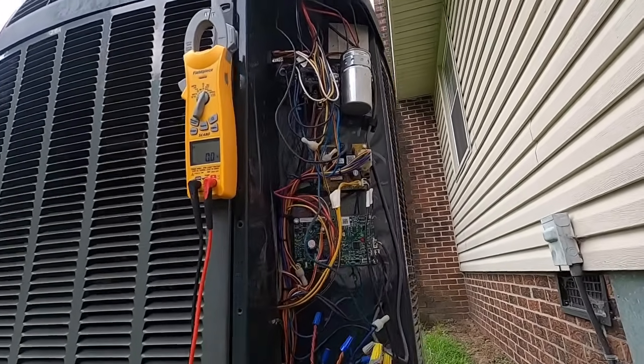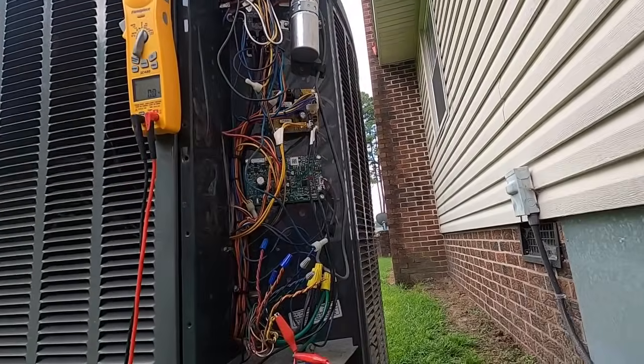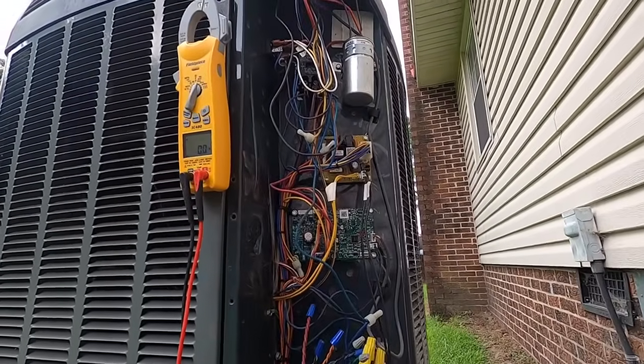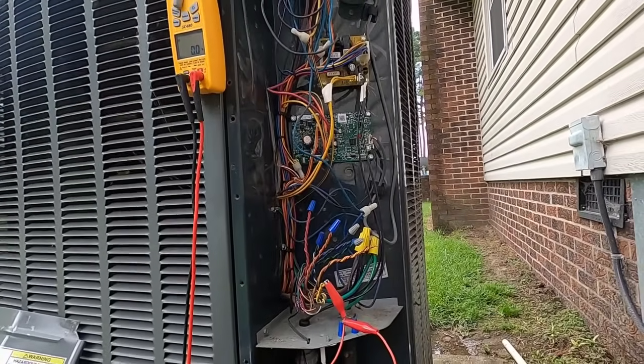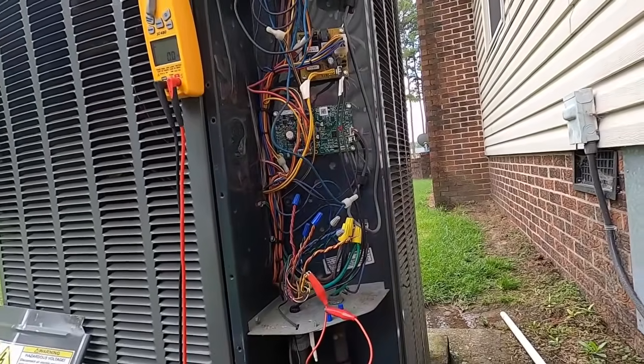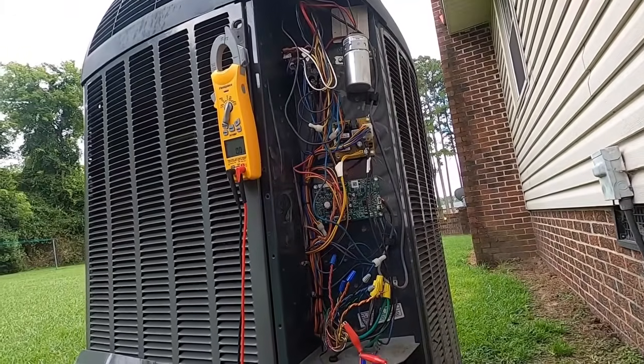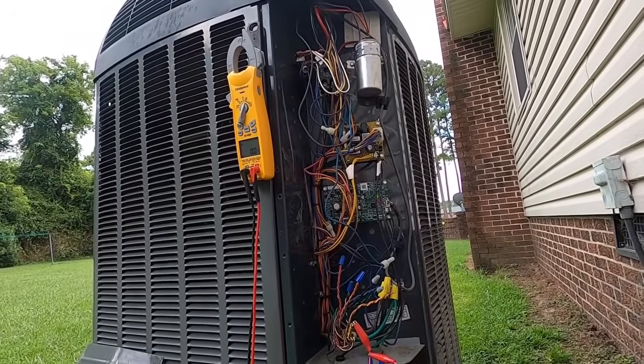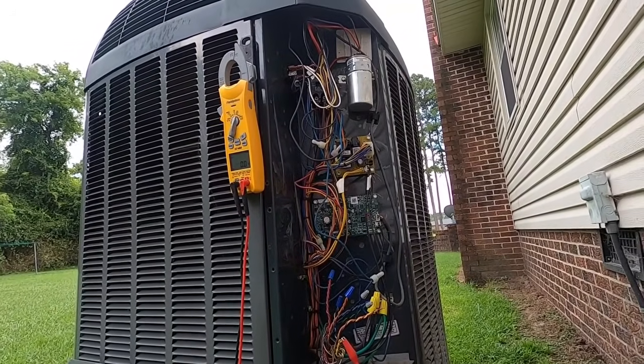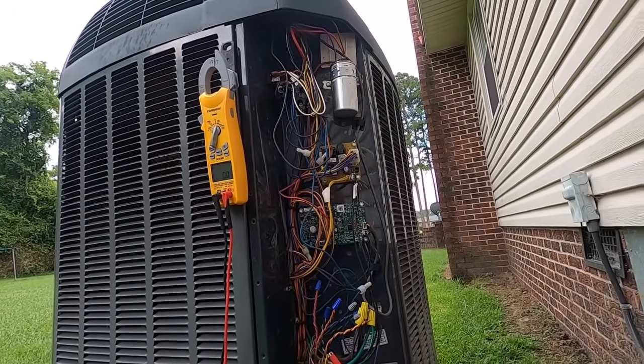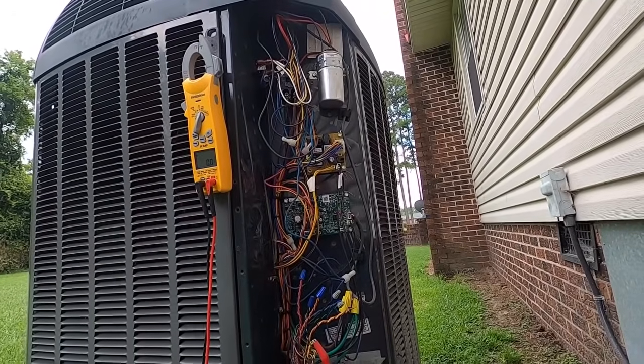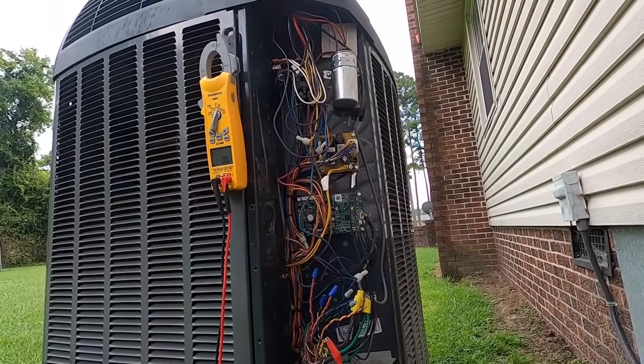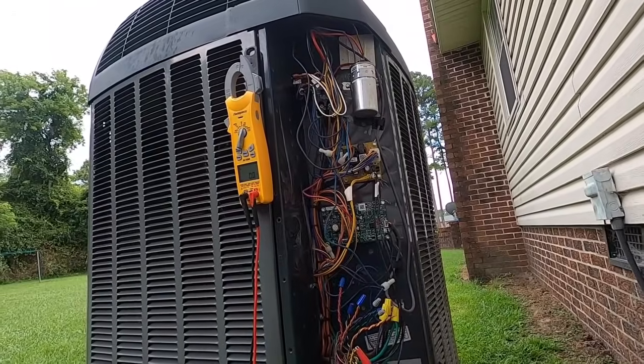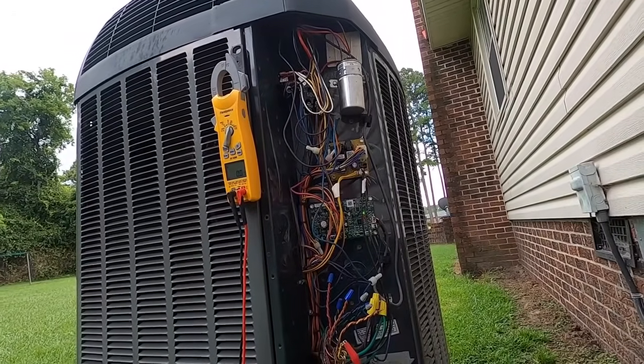We had a tech come out. This thing was shutting down on pressure lockouts and would run fine in first stage, and then when you put it in second stage, at least when he was running it in second stage, it would for some reason start to bog out and the pressures would start to just nosedive and go out on low pressure. So I'd seen this a couple of times.